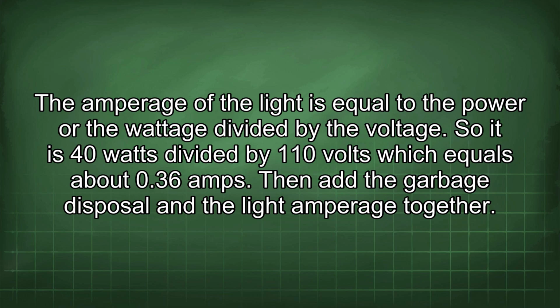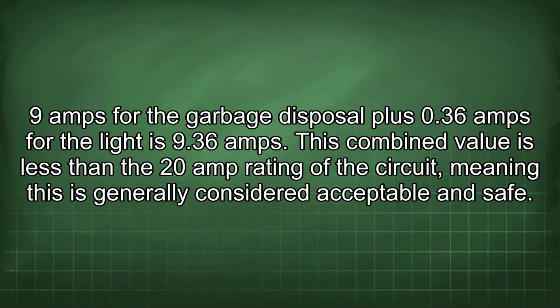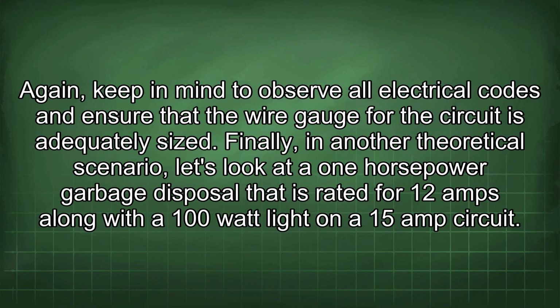Then add the garbage disposal and the light amperage together. 9 amps for the garbage disposal plus 0.36 amps for the light is 9.36 amps. This combined value is less than the 20 amp rating of the circuit, meaning this is generally considered acceptable and safe. Again, keep in mind to observe all electrical codes and ensure that the wire gauge for the circuit is adequately sized.